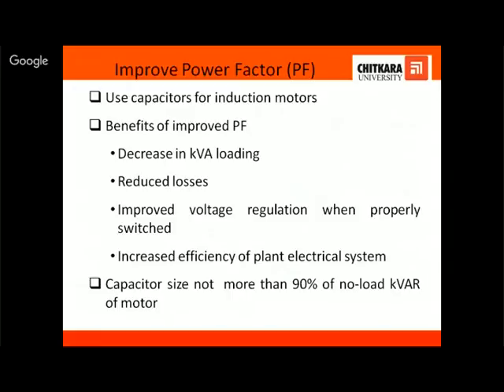When we have to start the induction motor, we go with capacitor switching. And when we are using the capacitor bank to improve the power factor of the system, make sure that the size of the capacitor is not more than 90% of the no load kVAR of the motor. Otherwise, the magnetizing current will become very high, and this condition is undesirable. So the capacitor rating should be kept up to 90% of the no load kVAR of the motor.